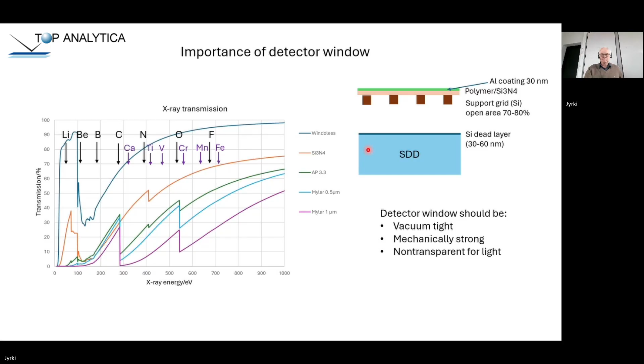Okay, this is my personal opinion, so you can skip it if you like, but I would say that for low energy work, especially if you are interested in X-rays below 1 keV, this is the best option. It has no absorption in a window and a high solid angle, but the problems are sensitivity to light and the electron trap. It's very difficult to build an electron trap here where the sensor is very close to the sample. The distance is only maybe 10-15 millimeters.